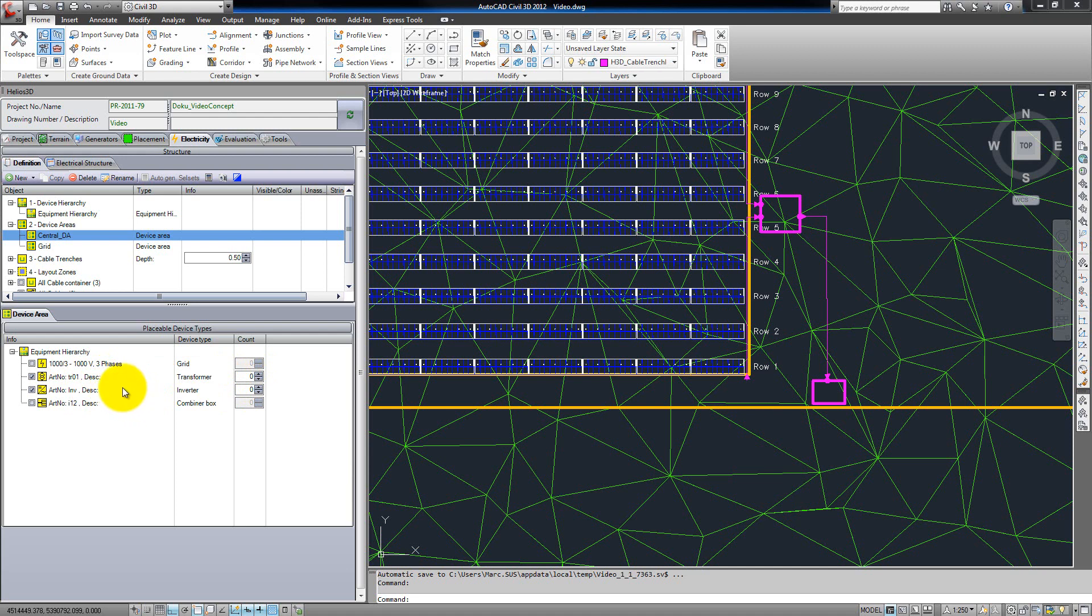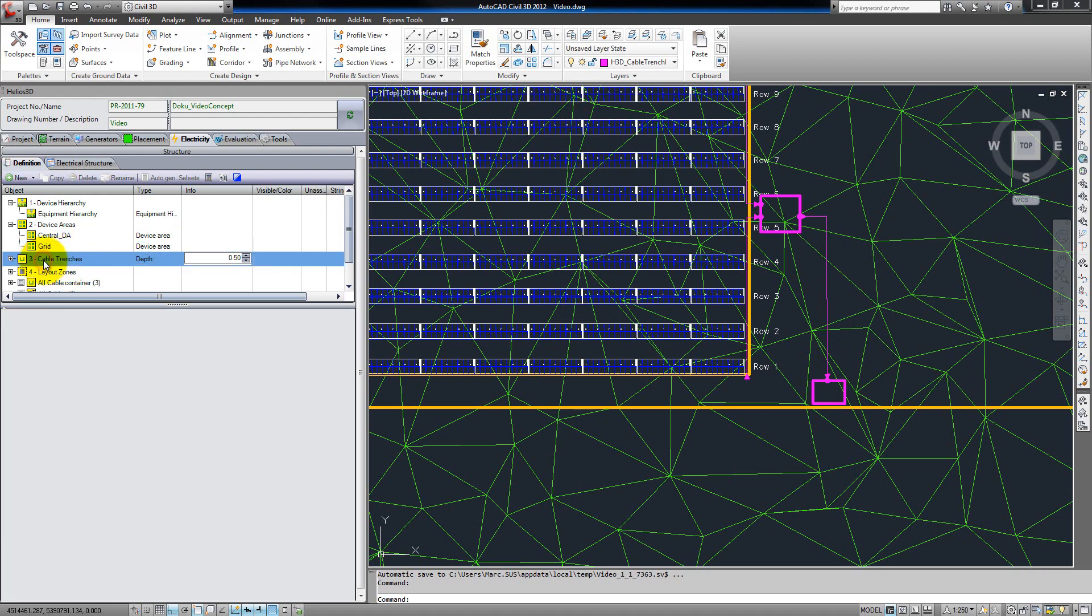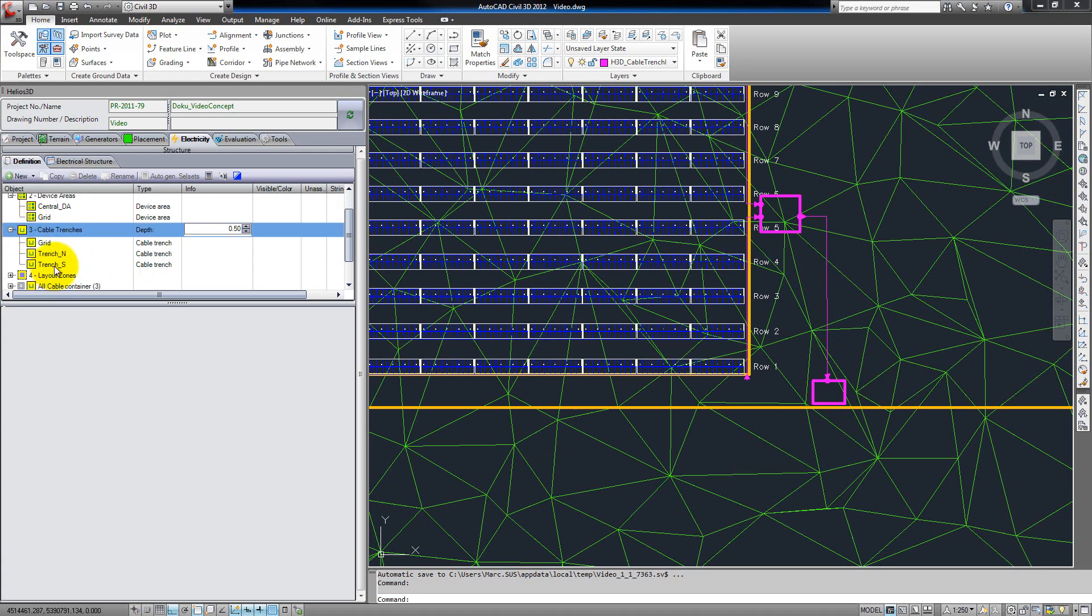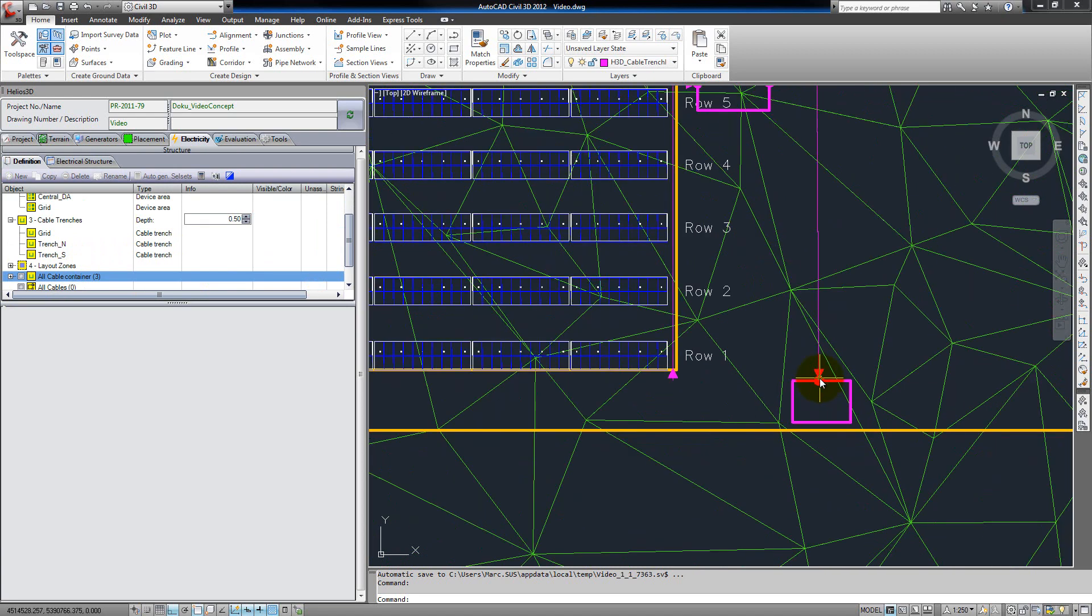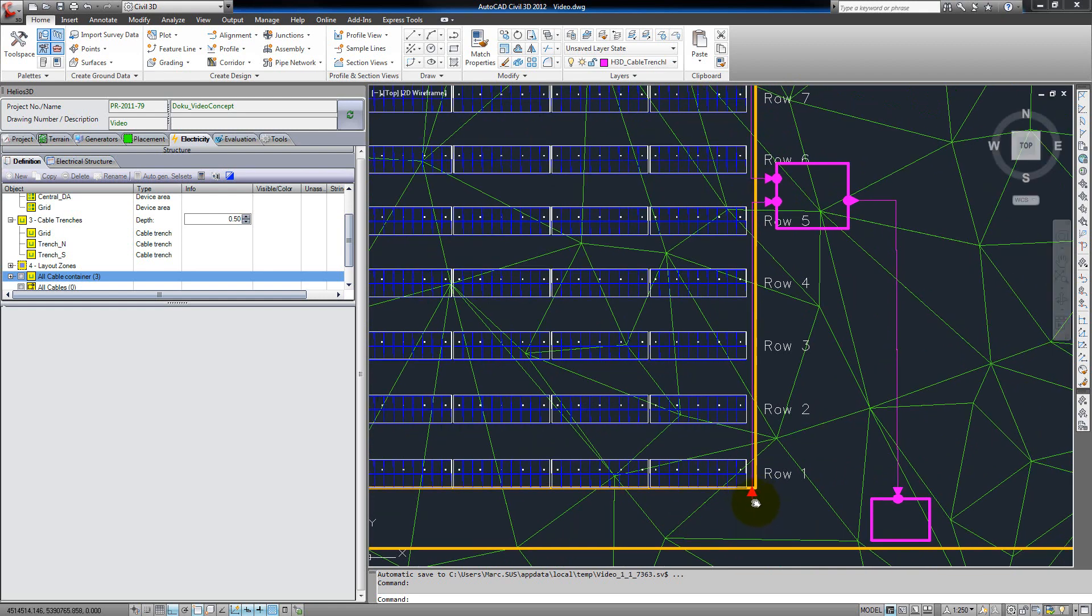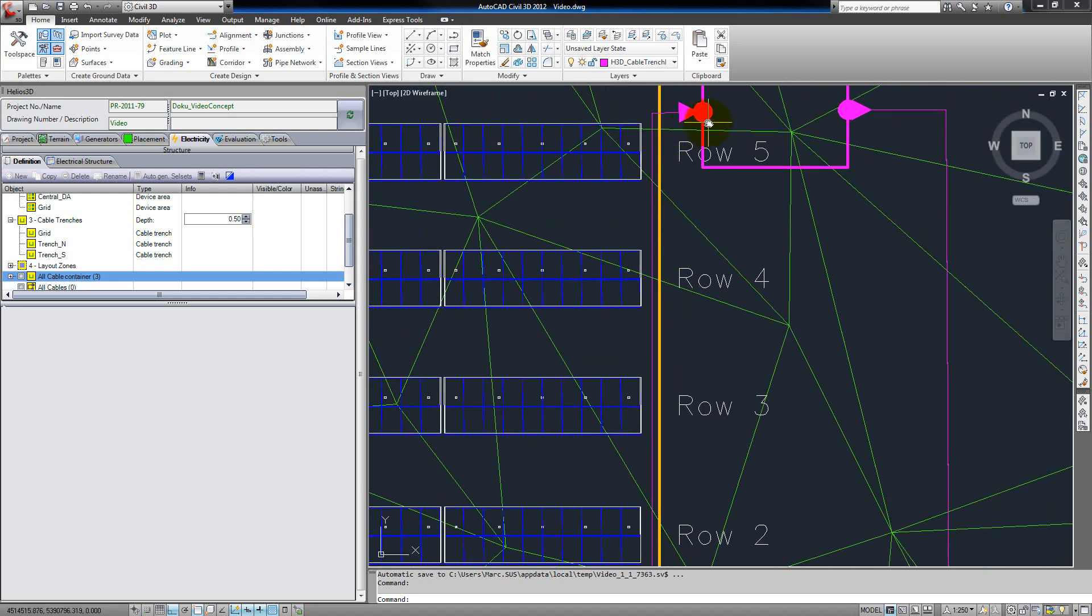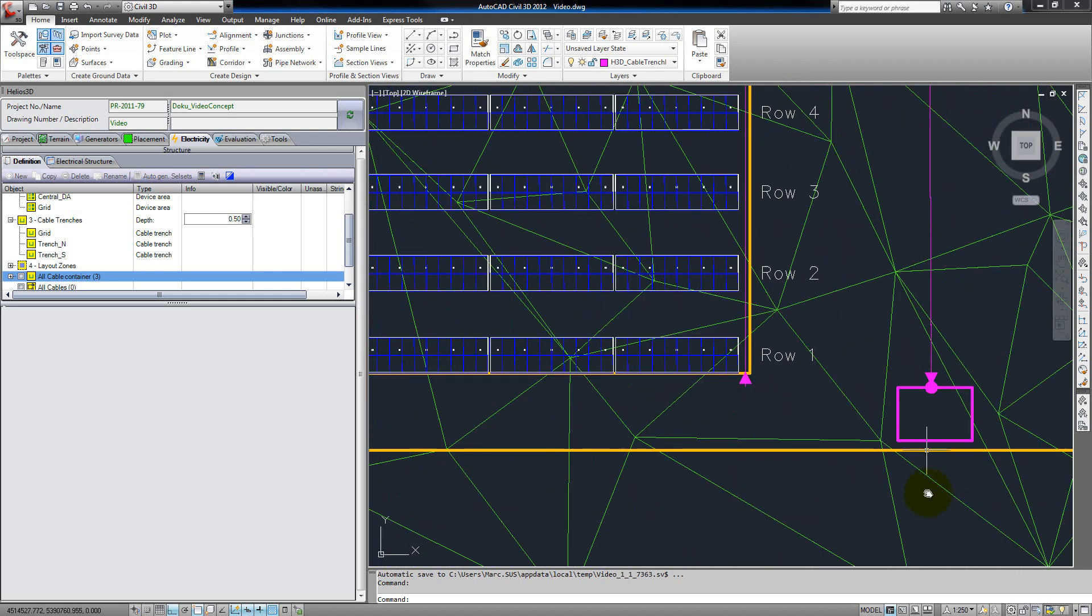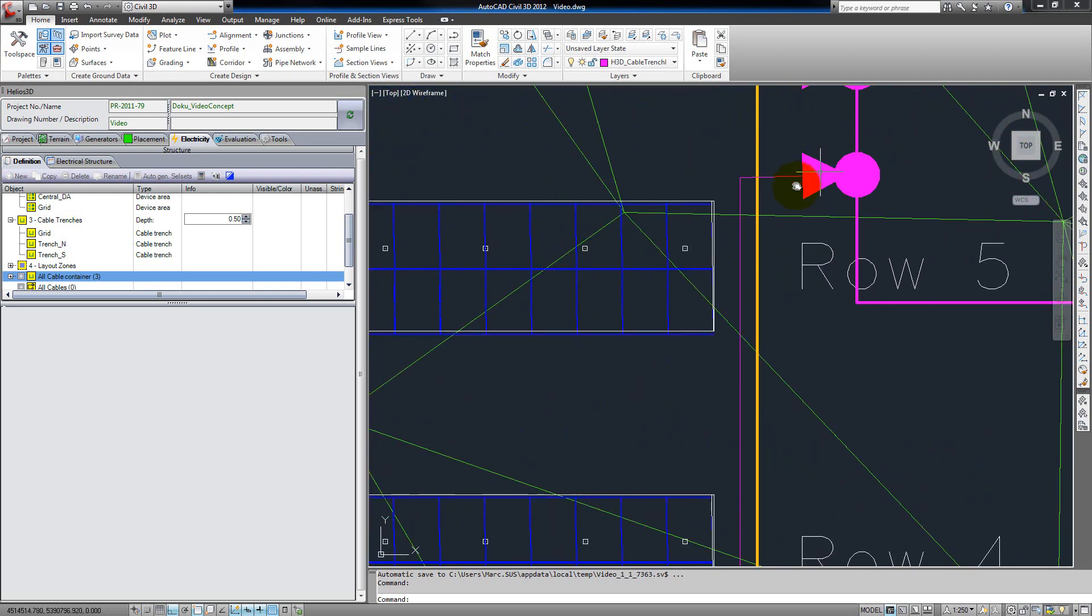One important thing about device areas is that we need at least one device area which includes the grid. Any device area which doesn't include the grid directly has to be connected to this device area by a cable trench. Building up cable trenches is our next point. The trenches are polylines which have to be connected to at least one device area. When the connection hierarchy is complete, so the cable trench starts here and is connected to a device area up to the grid, the flow of current is displayed at each end of the trench.